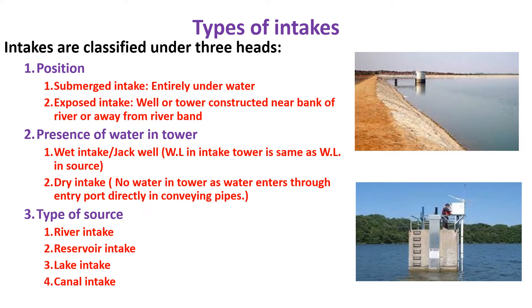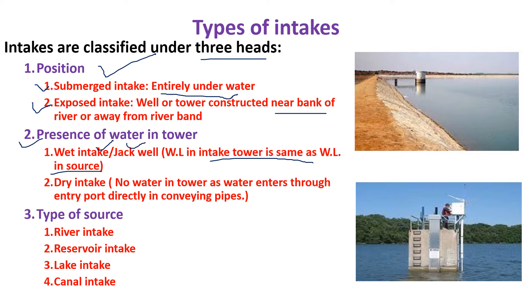There are three types of Intake classified under three heads. First, depending upon position: submerged Intake, which is entirely underwater, and exposed Intake, which is visible and generally constructed near the bank of a river. Second, based on presence of water inside the tower: if the water level inside the tower equals that in the source, it is called a wet well or jack well; if there is no water inside the tower and it is used only for valve operation, it is called a dry Intake. Third, based on the source: river Intake, reservoir Intake, lake Intake, and canal Intake.